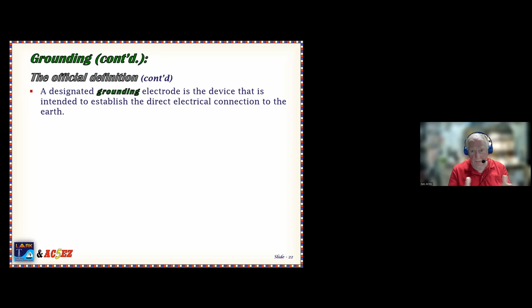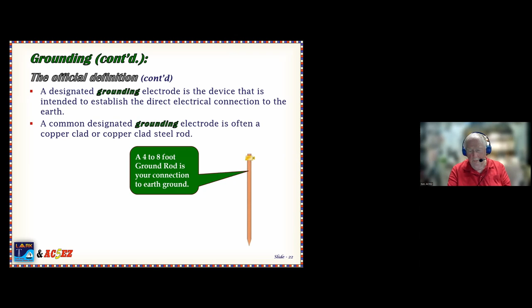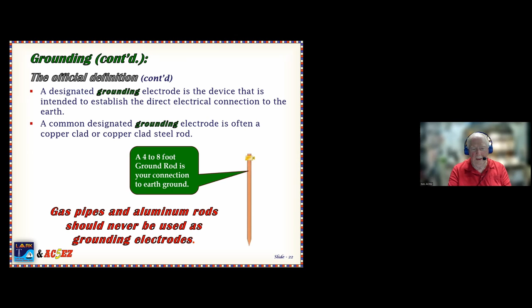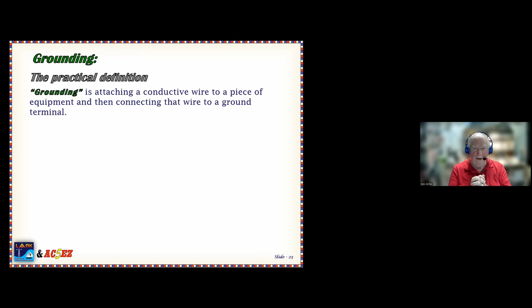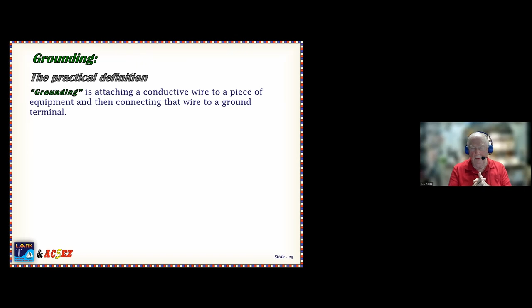Okay, a commonly designated grounding electrode, as far as amateurs are concerned, is often a copper clad steel rod. This is that 4 or 8-foot ground rod that you pick up at Lowe's or Home Depot. And by all means, do not attach your ground to gas pipes or aluminum rods. They should never, never be used. Gas pipes, well, you know what could happen there if you created a spark. Aluminum rods will oxidize and they will present a high impedance resistance to ground, which basically makes them null and void. Okay, grounding on a practical definition: grounding is attaching a conductive wire to a piece of equipment and then connecting that wire to a ground terminal.